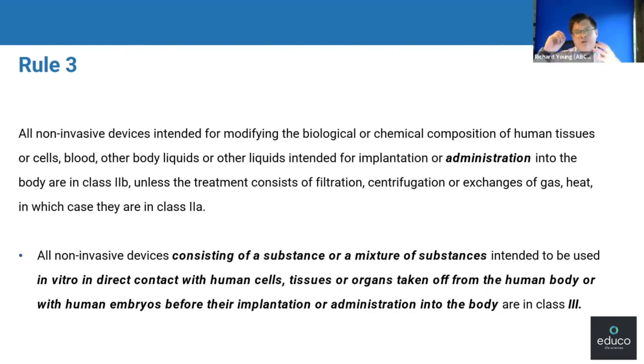It's also really important when you're reading those and the detail in these to be aware that the intended use of your product and the way your users actually use the product may change over time, which may change the classification of your product as well. So be aware of your classification when it comes to doing post-market surveillance, because it's complicated.